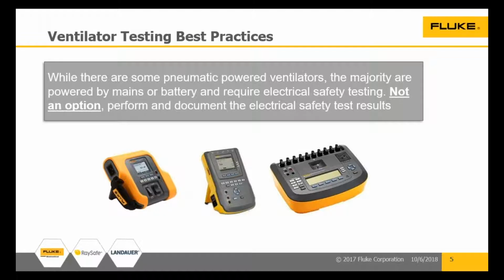When the patient touches the outside of the medical device, they form a pathway to ground, and some of the current is going to flow there. We need to know how much and what happens if. Okay. Does it have to be 10 inch? Probably not, but the size matters. That's why in the international standard they specify it in centimeters, but we'll use 10-inch. So you need enough conductive surface area in order to get a credible measurement. You will get a measurement. It's going to be low, but you need to just document how much is there. Okay, how much is there?